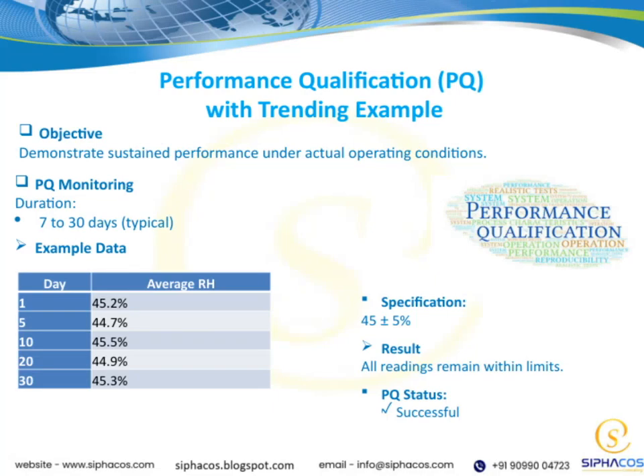Here, we see the results from our performance qualification, or PQ, testing. The specification called for relative humidity around 45%, plus or minus 5. And as you can see, all our readings stayed comfortably within that range over the full 30 days. This shows sustained performance under real operating conditions, exactly what we aim to demonstrate. The table gives a snapshot of average humidity at various points, confirming consistent control throughout the monitoring period. This trending example highlights the reliability of our system over time.